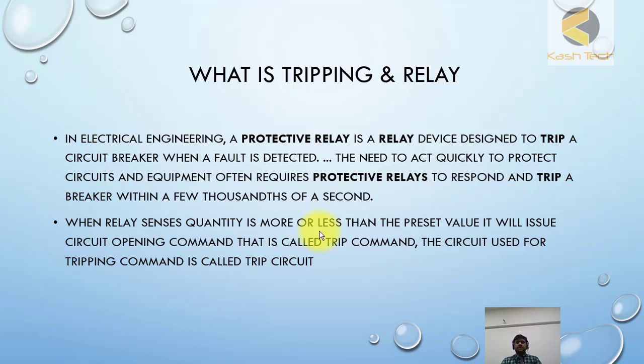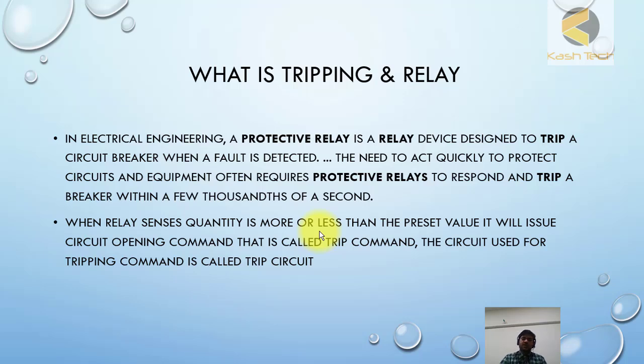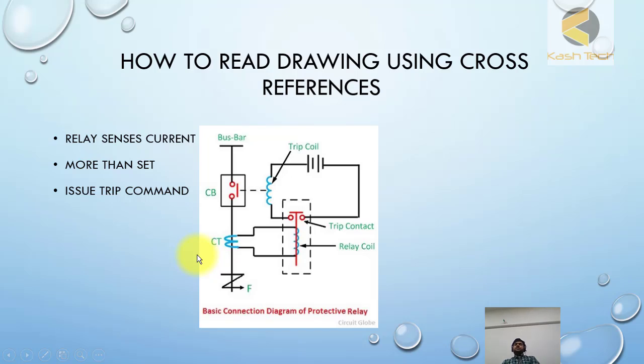The upper definition is a textbook definition. Simply put, a relay is a sensing device. Once the relay's sensed or measured value is more than the set value, after a preset time it will give the tripping command. The tripping command is issued, the contact of the relay will operate, and the circuit will close — this is then called a tripping circuit. The tripping command is issued and the breaker will trip. This is how the tripping relay and tripping command work.